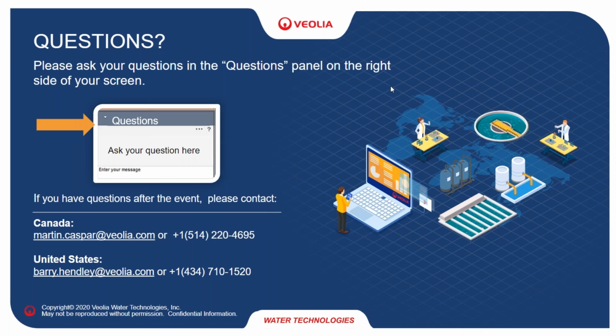Okay, a question on, should the agitation speed be varied depending upon flow rate or other conditions? I know that it can be, but I'm just going to say off the cuff, no. I know people disagree with me, especially, but I think decreasing that during times of really low turbidity and low flow can help to save energy, but no is going to be my answer. That wouldn't be even my top 10 thing to do to save energy.